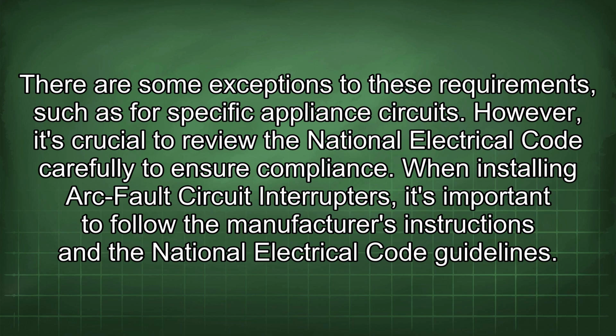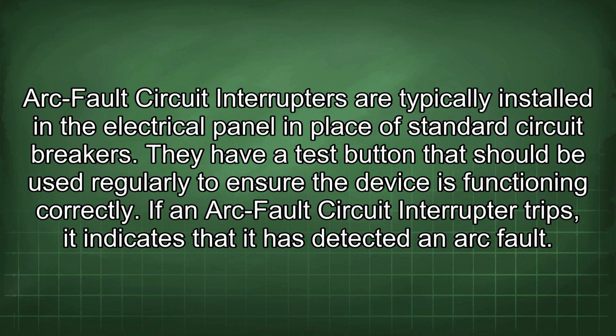When installing arc fault circuit interrupters, it's important to follow the manufacturer's instructions and the National Electrical Code guidelines. Arc fault circuit interrupters are typically installed in the electrical panel in place of standard circuit breakers. They have a test button that should be used regularly to ensure the device is functioning correctly.